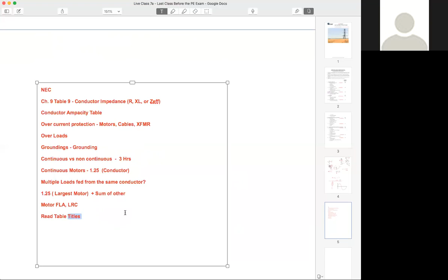Someone asked, do we multiply three-phase continuous motor by 1.25? Yep. Essentially you're taking that full load amps and multiplying it by 1.25 to find your conductor rating. If it's a three-phase motor, that full load amps is being pulled on each of the three individual conductors serving each phase. So yeah, you still need to increase that ampacity.